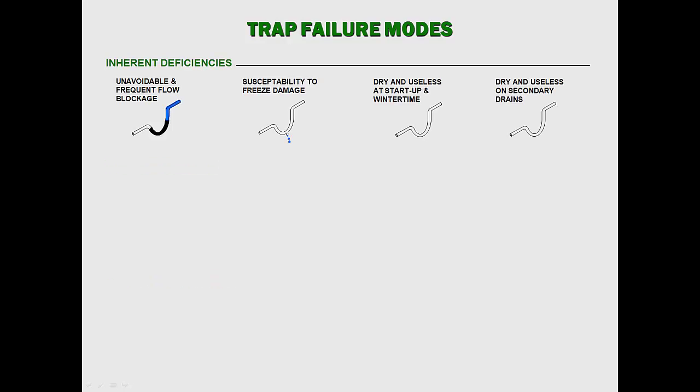The trap failure modes identified by ASHRAE can be divided into three categories: those due to inherent trap deficiencies, trap design deficiencies, and unwise field practices. Inherent trap deficiencies include unavoidable and frequent flow blockage, susceptibility to freeze damage, dry and useless at start-up and wintertime, and dry and useless on secondary drains. These deficiencies are common to any trap, regardless of the design.